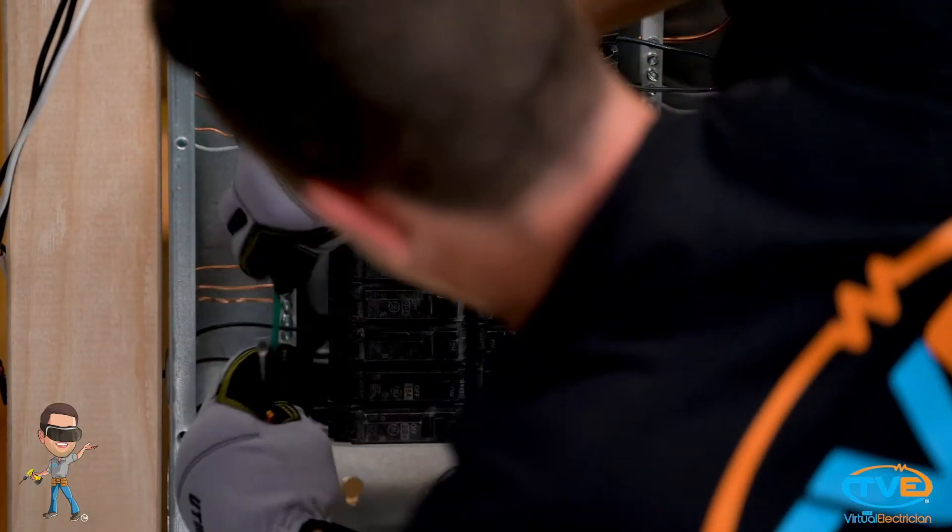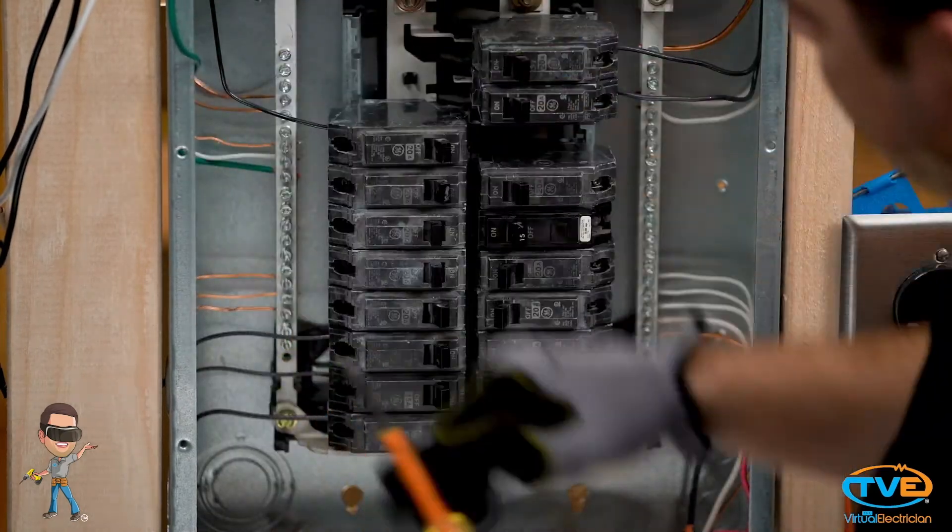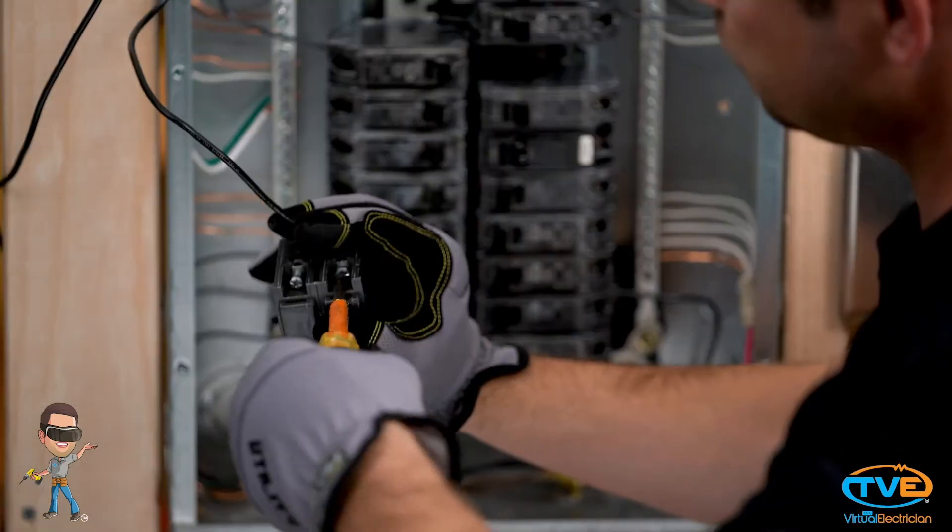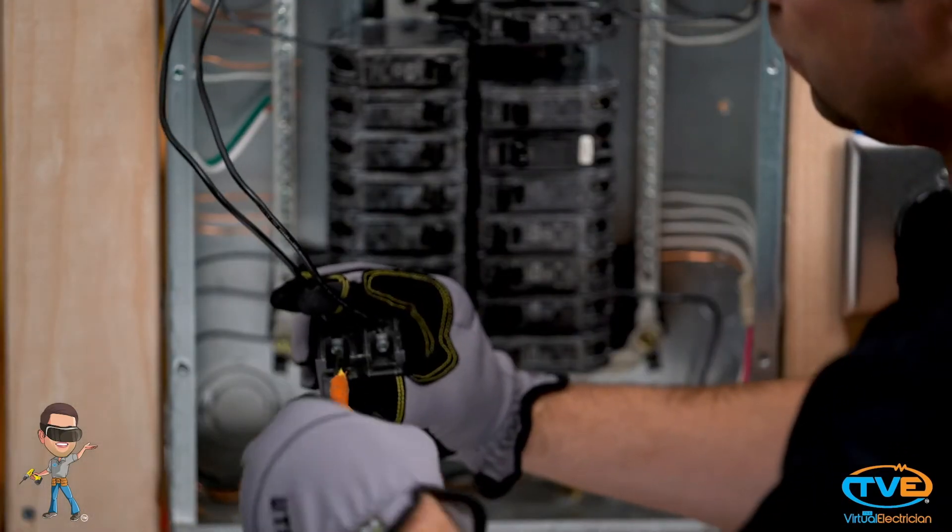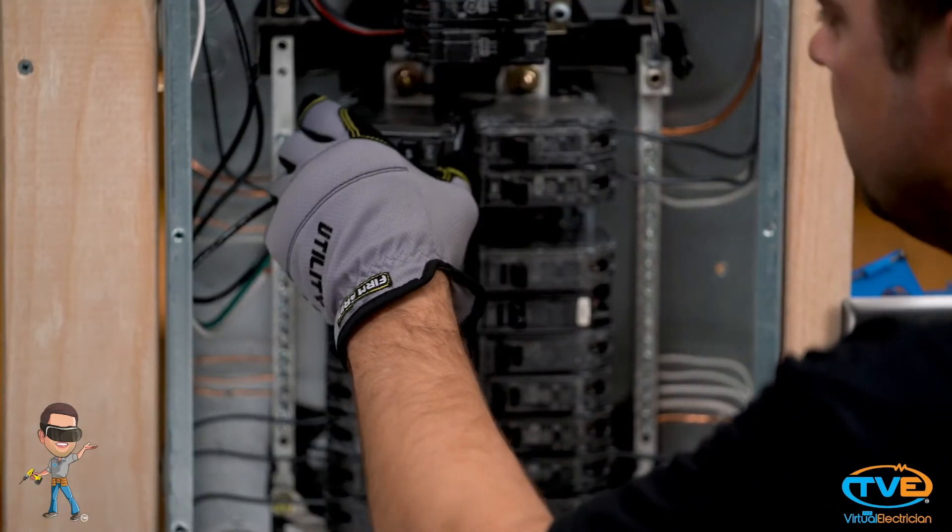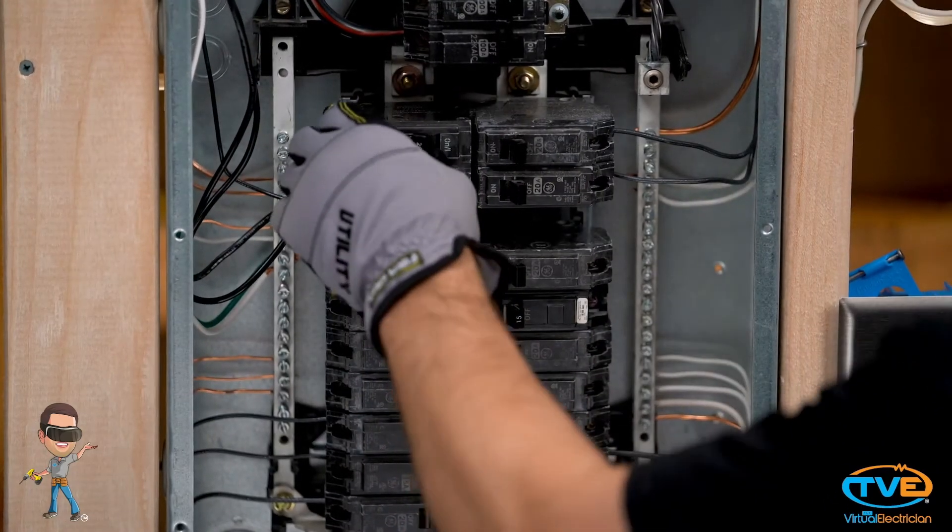Next, you wire it up like you would a 240-volt circuit. Ground first, then neutral, and then the two other wires will go on the breaker. One that will protect phase A and the other that will protect phase B.